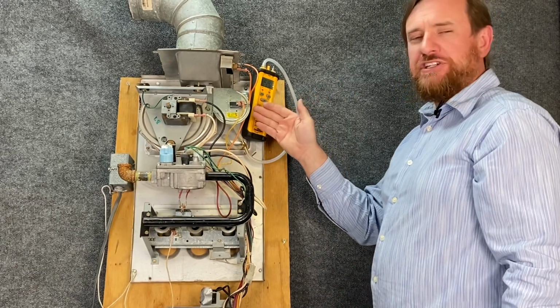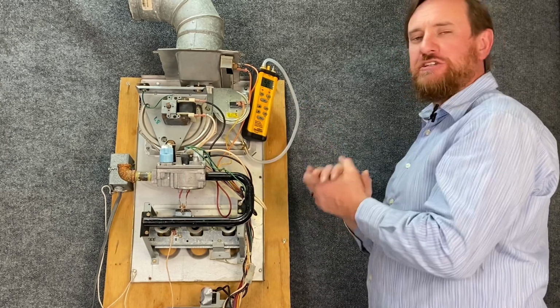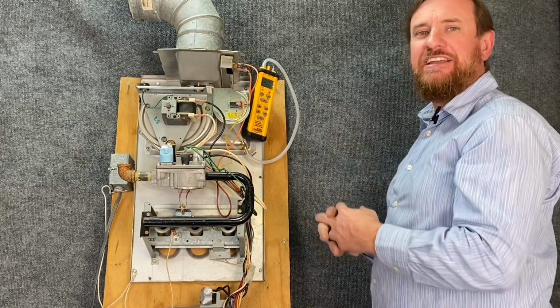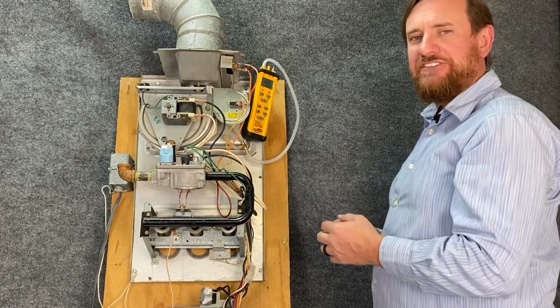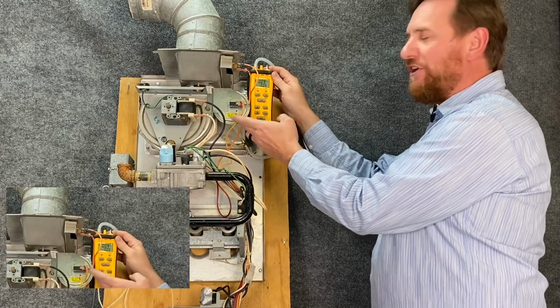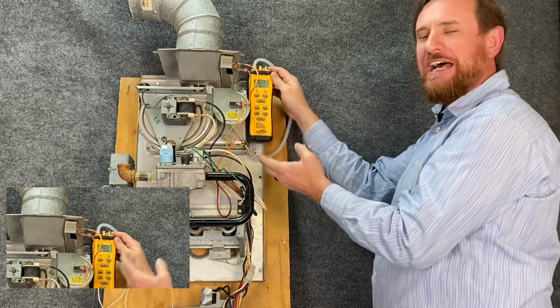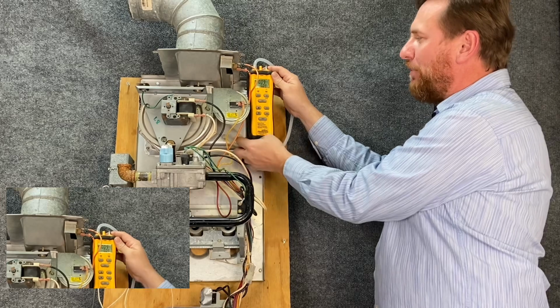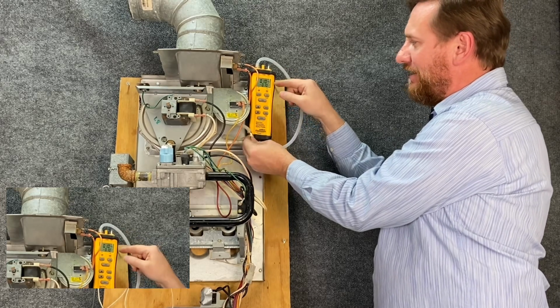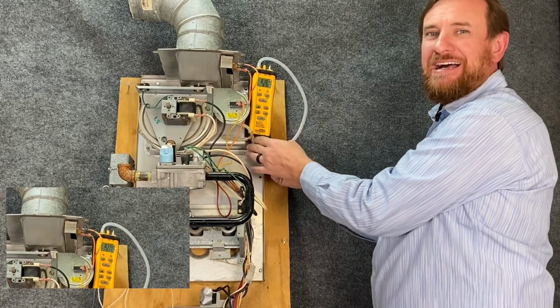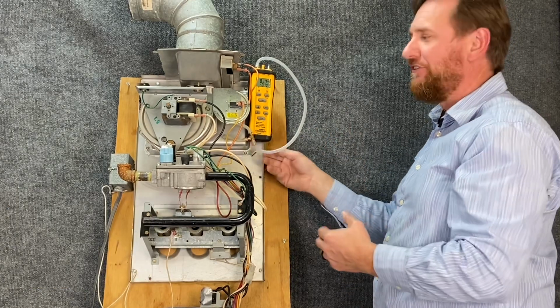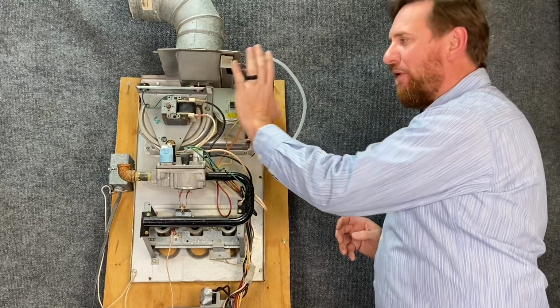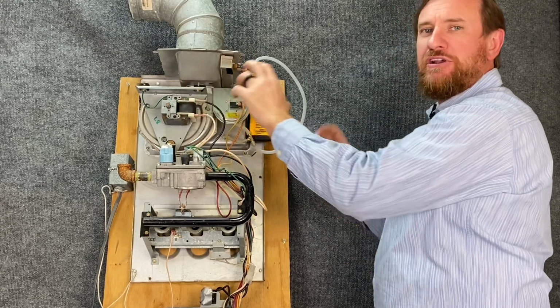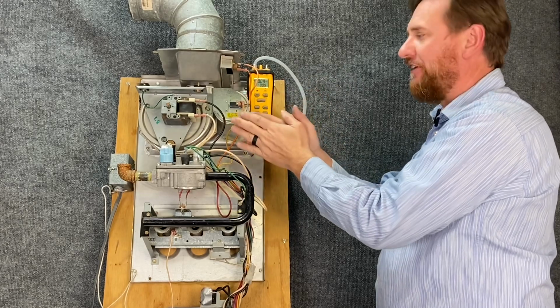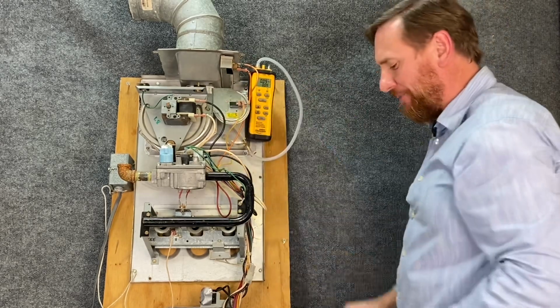You could think, well, the switch isn't closing and I want it to close, let's replace the switch. That would be wrong. That's like saying your gas gauge is on E, I need to get a new gas gauge. Do you have gas in the car? In this case, we need to be thinking, my switch isn't closing, it's a vacuum pressure switch. Do I have enough vacuum? And the answer is no. I only got 0.1 inches of water column. In this case, it's jumping around a little bit, but 0.1 inches of water column. I need 0.25 inches of water column for this to close. So I need to be looking on the fan side. What's going on here? Let me check that inducer fan motor, go through all that process to make sure that's working first. It's not a problem with my switch. It's on this side. So I'm going to make a minor adjustment to this unit.